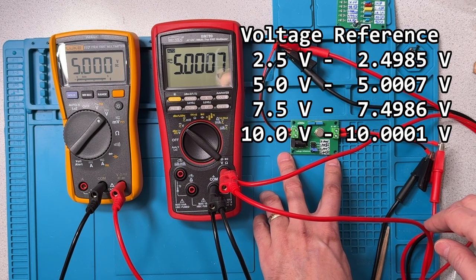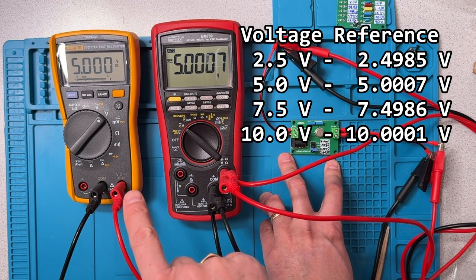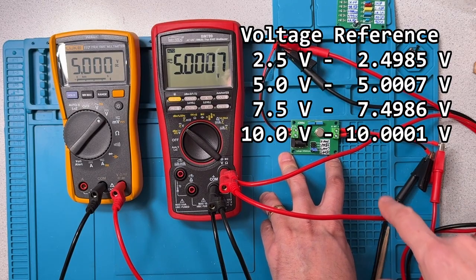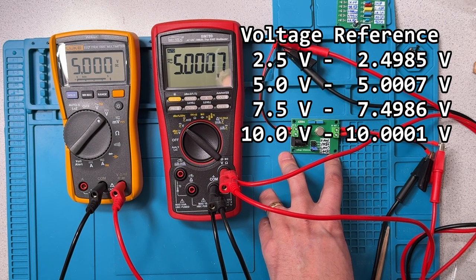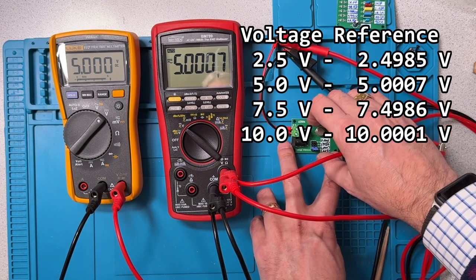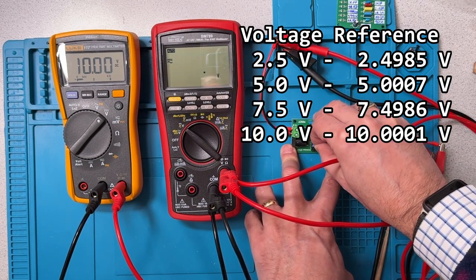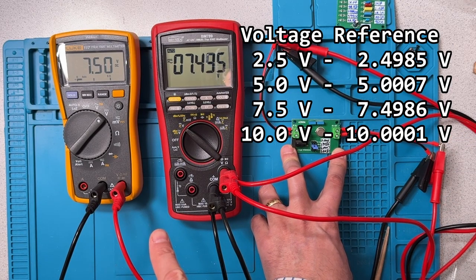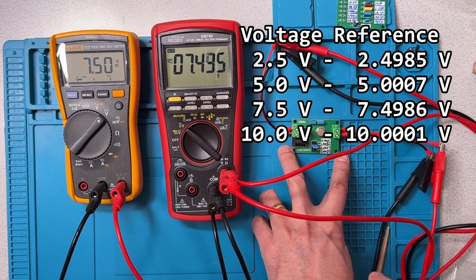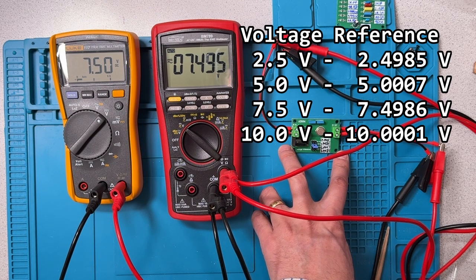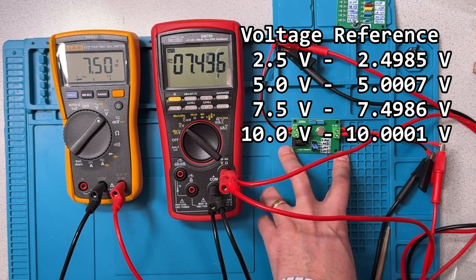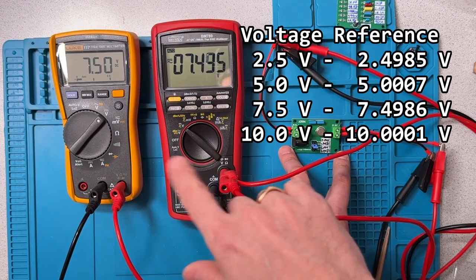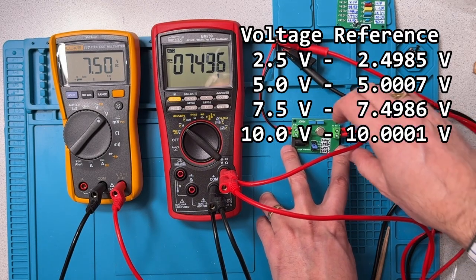So this is now 5 volts, and so the Fluke is showing 5.0 volts dead on. The calibration source shows 3 zeros and a 7, and the Brymen is showing exactly that. Let's go to the next step at 7.5 volts. So the Fluke is showing 7.5 volts. The reference source shows that it was 7.4986. We've got here 7.495 or 6. So a little more accurate once again on the Brymen. Of course, because it's a 60,000 count meter, we're losing that first leading digit, so it's shown as a 0.